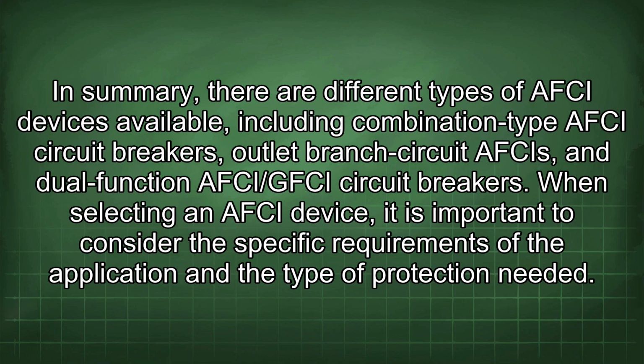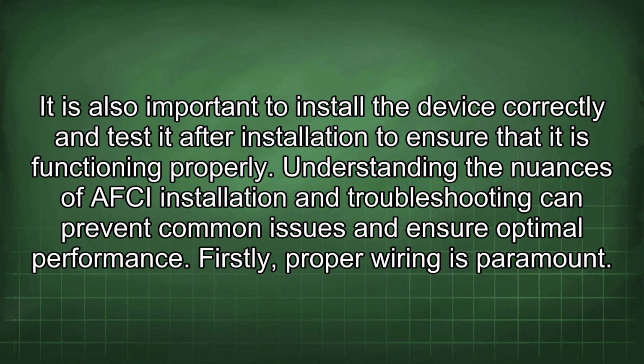In summary, there are different types of AFCI devices available, including combination type AFCI circuit breakers, outlet branch circuit AFCIs, and dual function AFCI/GFCI circuit breakers. When selecting an AFCI device, it is important to consider the specific requirements of the application and the type of protection needed. It is also important to install the device correctly and test it after installation to ensure that it is functioning properly. Understanding the nuances of AFCI installation and troubleshooting can prevent common issues and ensure optimal performance.